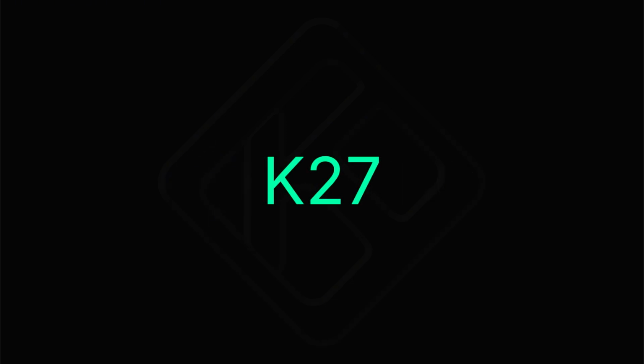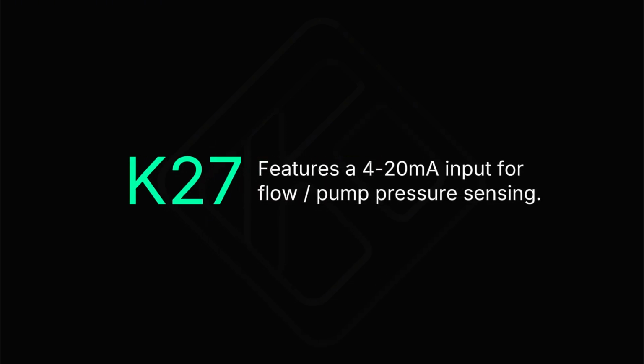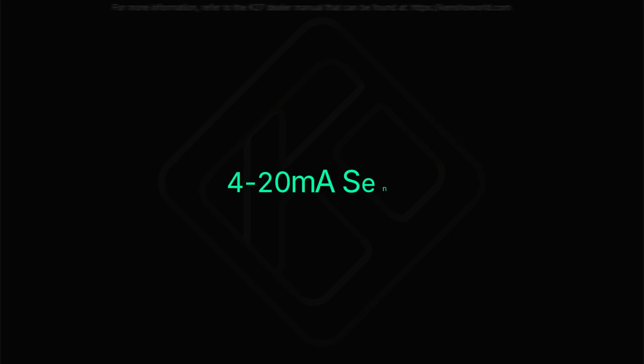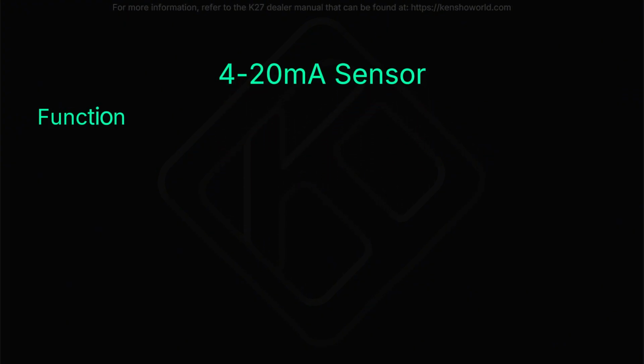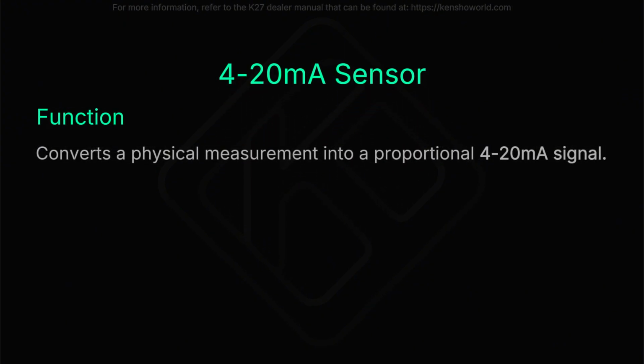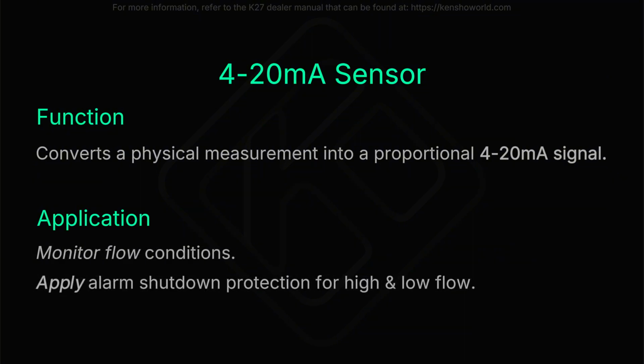The K27 engine control panel features a 4 to 20 mA input for flow or pump pressure sensing. In this video, learn how to wire, connect, and set up a 4 to 20 mA flow sensor. The 4 to 20 mA sensor converts a physical measurement, such as flow in liters per second, into a proportional electrical signal that can be read by the controller. The 4 to 20 mA sensor allows the controller to monitor flow conditions and apply alarm shutdown protection for high and low flow.